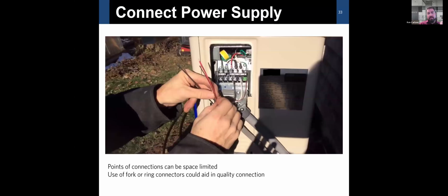While you're pulling your vacuum off, that's the time you'll start making your power connections. Space is limited, particularly in the mini split. It's stranded wire. I'd recommend, depending on what your connection terminal is like, often using fork or ring connectors, which aid in the quality of the connection. You crimp a fork connector onto your wire, put the fork connector underneath the screw, and clamp it down. That ensures a nice firm, tight connection that's not going to wiggle loose, and a good quality connection. Stranded wires tend to squeeze off to the side, and sometimes you don't have the whole wire sitting underneath and making good contact.